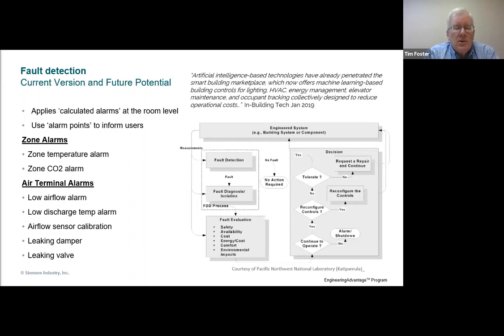The difference between a fault detection and an alarm. In your car, the oil temperature light, that's probably an alarm. That's a single sensor, discrete point, wired to a light on your dashboard. It tells you that you have an alarm. It really doesn't tell you the problem that was causing that, nor could it have told you in advance that was going to happen.